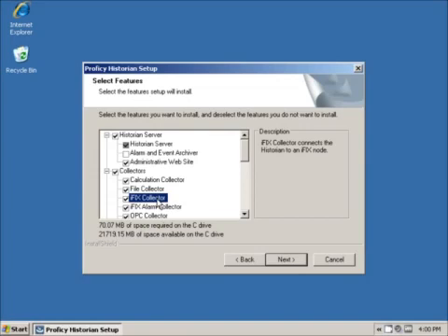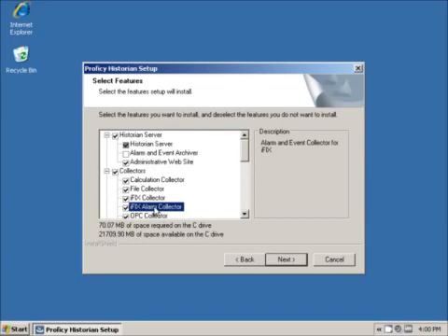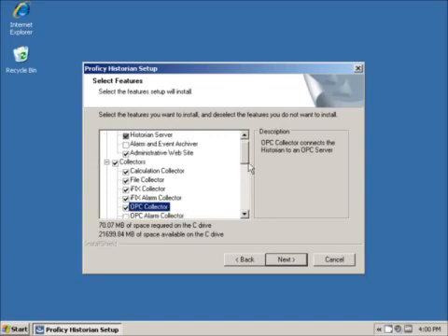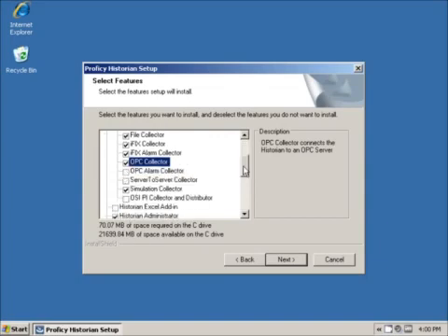The iFix collector is for pulling data from Proficy iFix. The iFix Alarm and Event Collector is designed to capture Alarm and Event data from iFix through the Alarm and Event OPC server. The OPC Collector is for taking data directly from OPC servers, such as the GE Industrial Gateway Server or Rockwell RSLinx. It installs a different instance for each OPC server on the same computer.